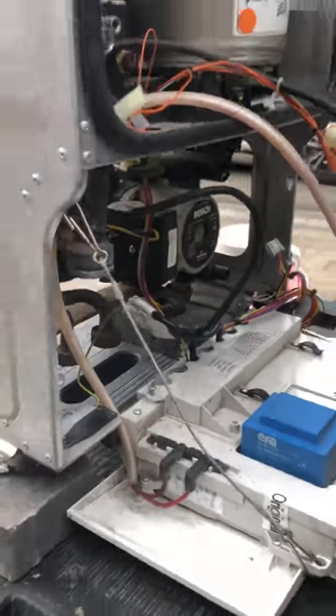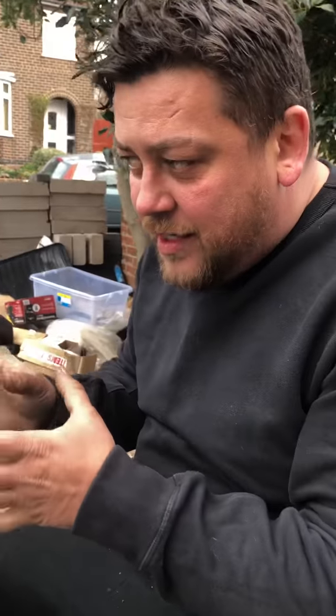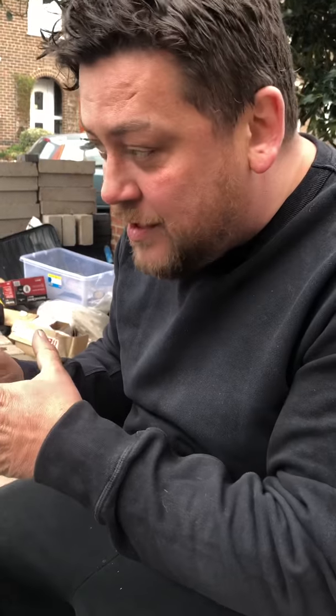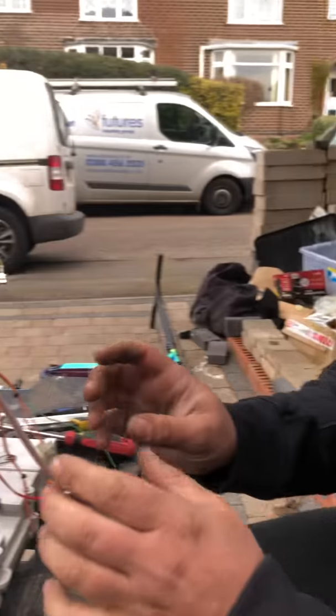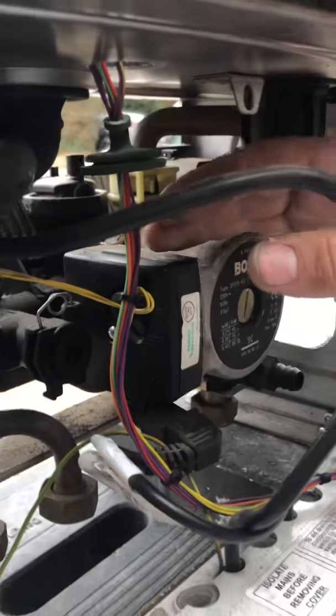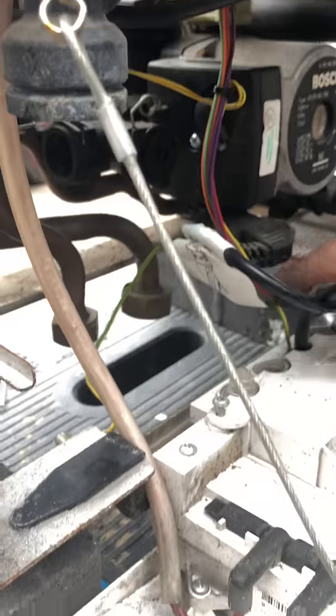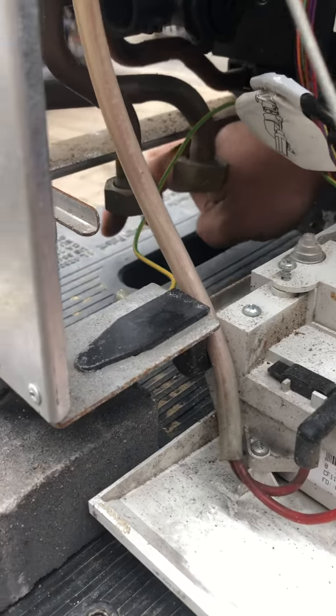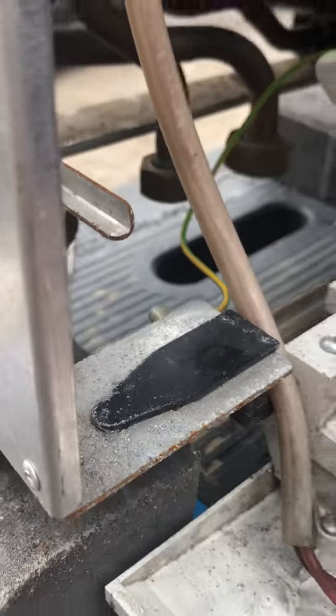Now, what will happen now is you've got to try and get that heat exchanger out with the boiler in position. Now, it's possible, but the best way to do it is to remove the cold and the hot pipe underneath. Just cut through them, take them out of the way, drop the heat exchanger down and fish it out, because you're going to struggle to get it past the hydraulic block otherwise, whereas you can actually drop it down and just remove a couple of pipes that will be in position down here, just a small section, and then just recouple them again afterwards. So we've slacked the screws off.